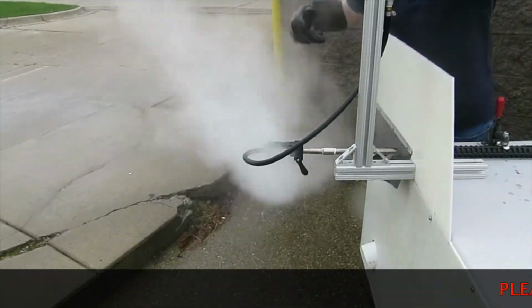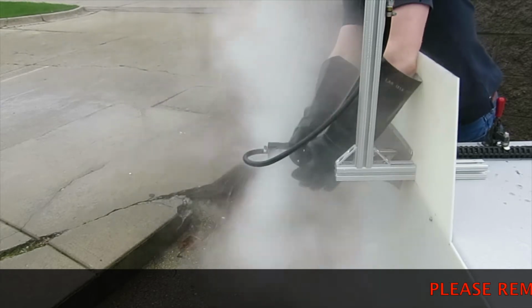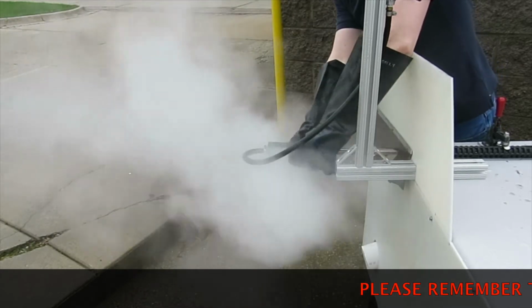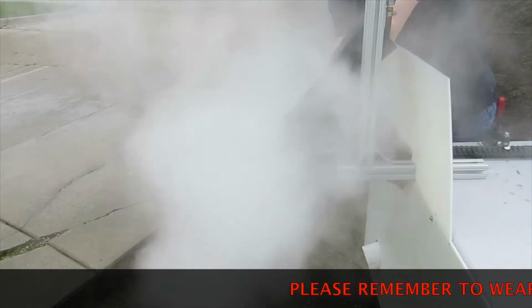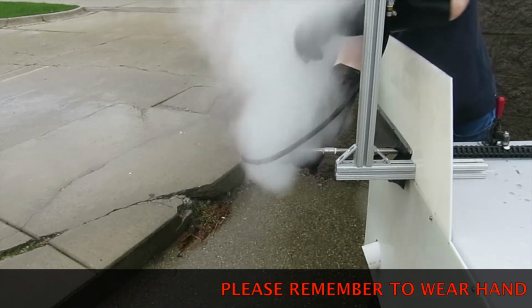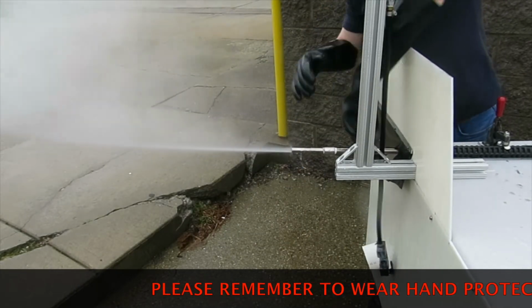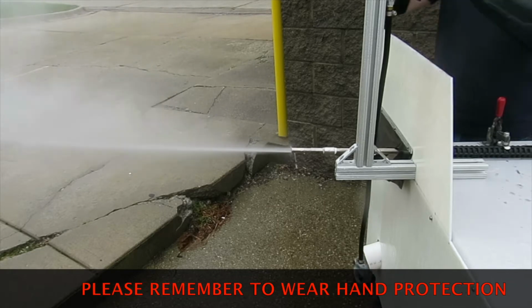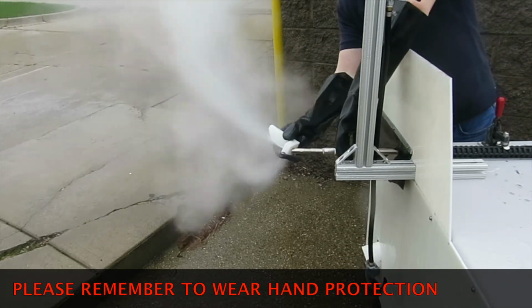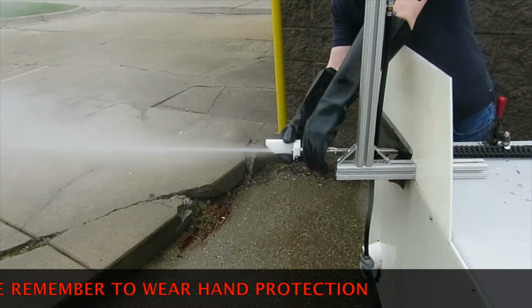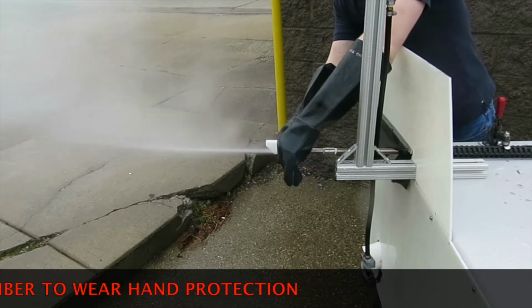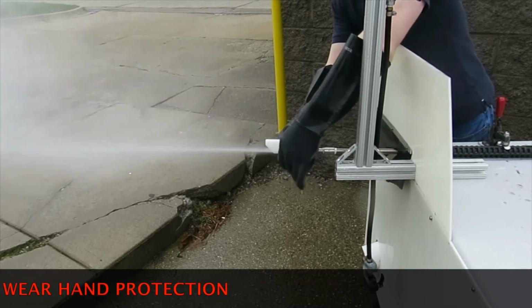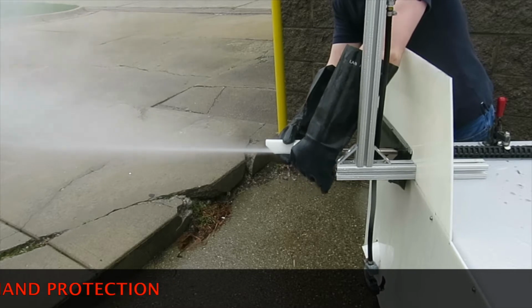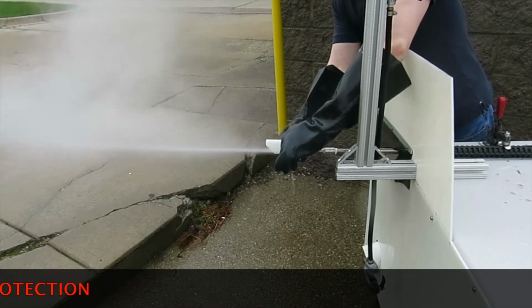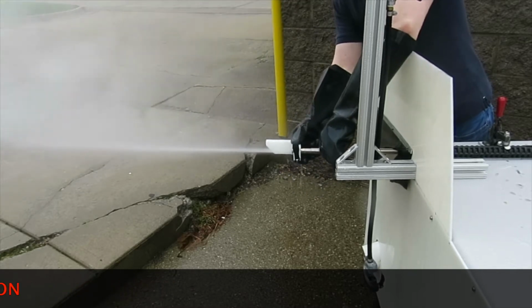Once the dynamic head pressure has been set, it's time to remove the dynamic head fixture wand adapter and reinstall the wand foot. We are going to show you how this is accomplished on the outdoor mobile workstation so you have a better view of the entire process. Please remember to wear hand protection. You are now ready to perform an actual thermal shock test.